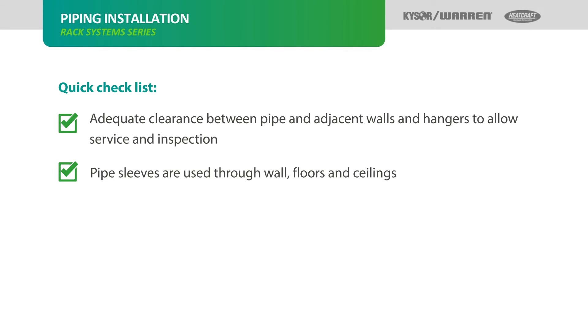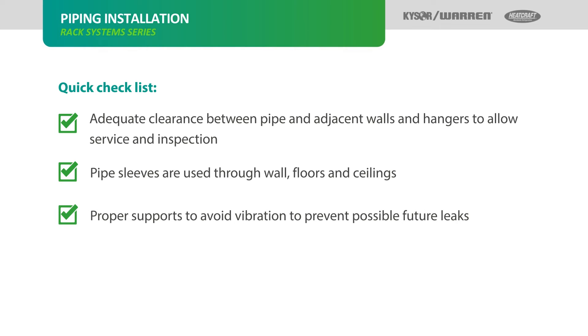Piping Installation. A quick checklist for proper installation of insulation: adequate clearance between pipes and adjacent walls and hangers to allow service and inspection; pipe sleeves are used through all walls, floors, and ceilings; proper supports to avoid vibration to prevent possible future leaks.